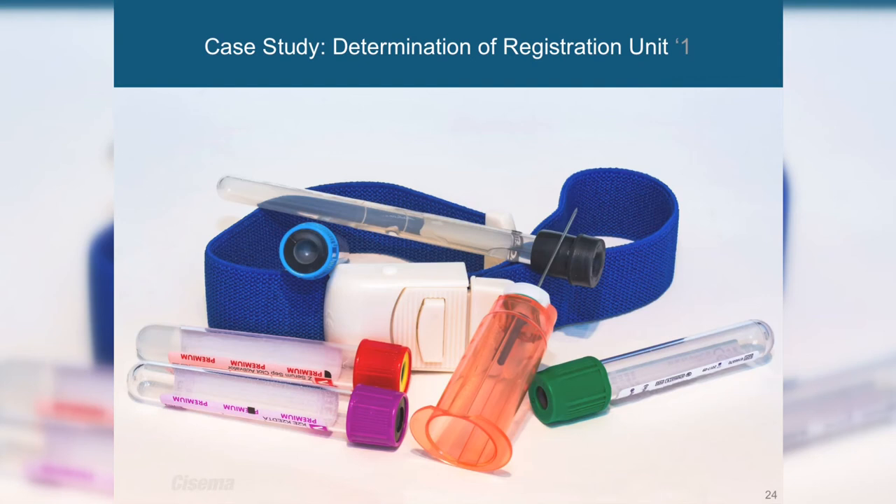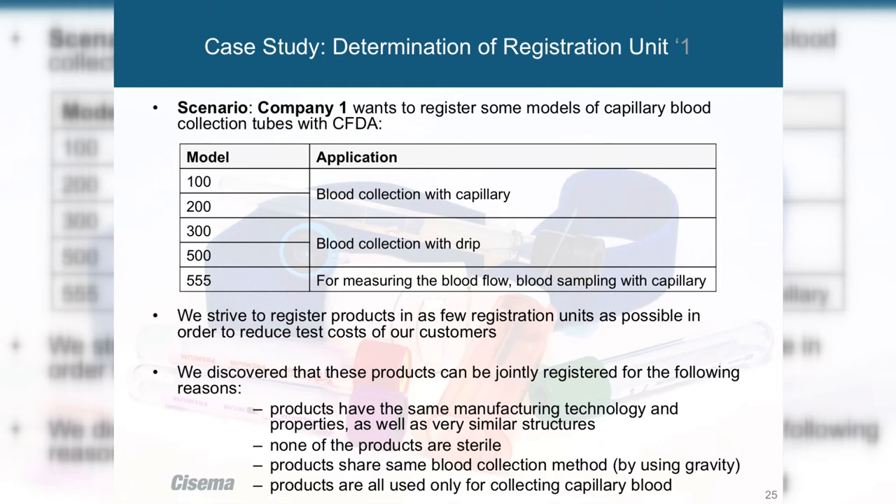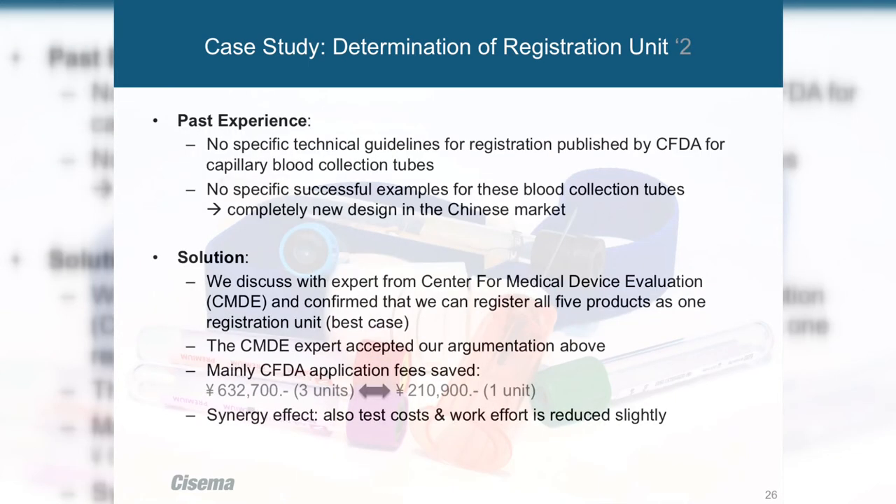Here's a case study on the determination of registration units, which can save a lot of effort and money. A company wanted to register models of capillary blood collection tubes. We discovered the mode of use and application were very similar, so we consulted experts from the Center for Medical Device Evaluation. They confirmed it was possible to register all products within one unit, saving our customer significant money and effort.